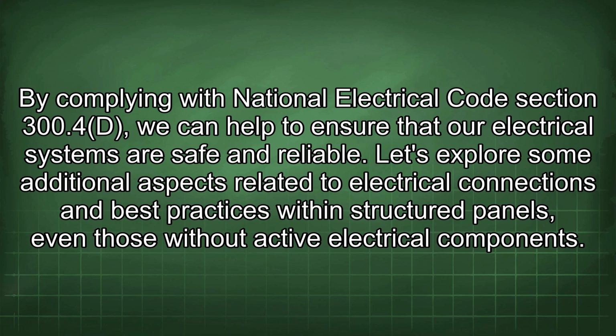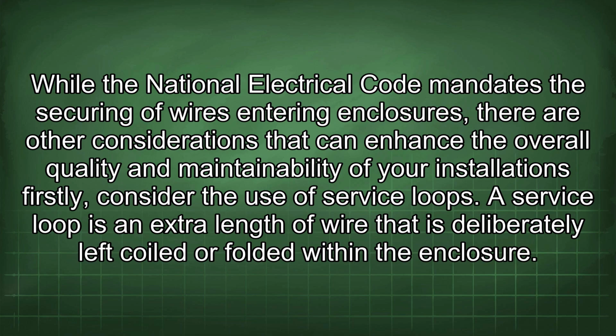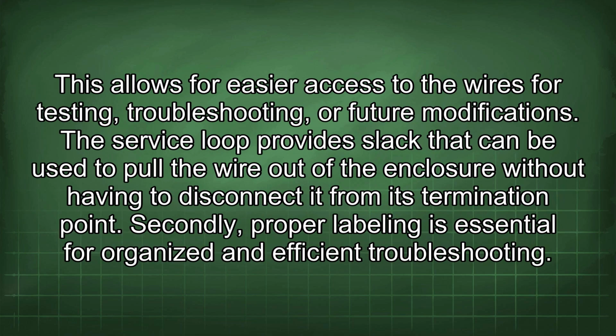Let's explore some additional aspects related to electrical connections and best practices within structured panels, even those without active electrical components. While the National Electrical Code mandates the securing of wires entering enclosures, there are other considerations that can enhance the overall quality and maintainability of your installations. Firstly, consider the use of service loops. A service loop is an extra length of wire that is deliberately left coiled or folded within the enclosure. This allows for easier access to the wires for testing, troubleshooting, or future modifications. The service loop provides slack that can be used to pull the wire out of the enclosure without having to disconnect it from its termination point.